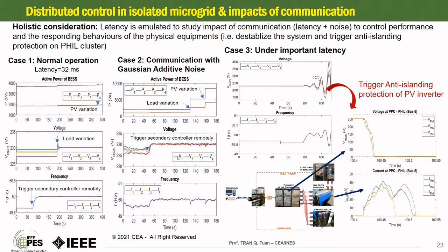Third case, under important latency. In this case, we add 500 milliseconds to the latency to investigate the behaviors of controllers in a bad communication scenario. For this case, when the secondary control starts here, the controllers fail to stabilize the microgrid, as illustrated in this figure. The overvoltage triggers the protection, the anti-islanding protection of the PV inverters. Finally, the grid becomes unstable. The controllers therefore need to be modified to adapt to the new working condition.